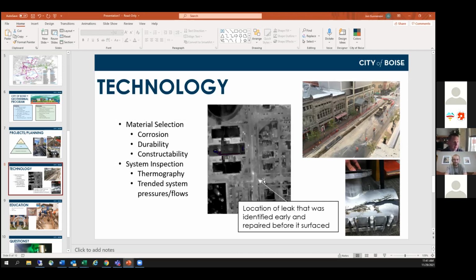Corrosion was identified very early on in the system, so there have been different attempts to prevent it. Originally a lot of the valves and couplers were direct buried, and with the hot water and soil contact, those steel fittings would just crumble within a matter of years. So we put a lot of those in vaults to eliminate the soil-metal interface, and then started using different stainless steel couplers.